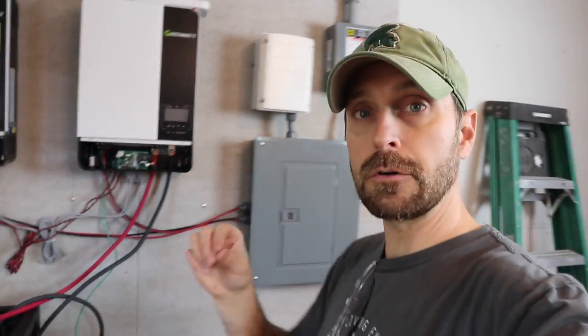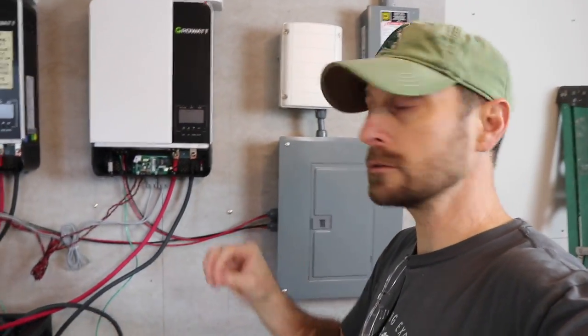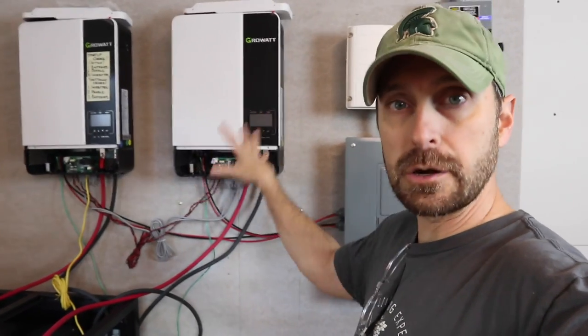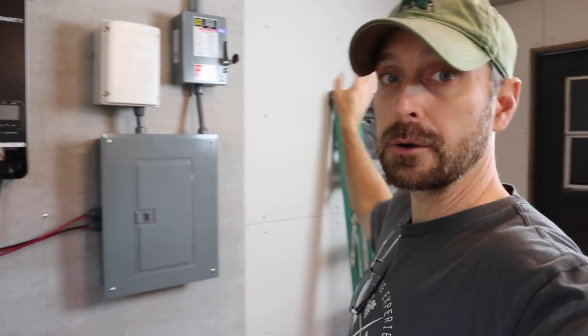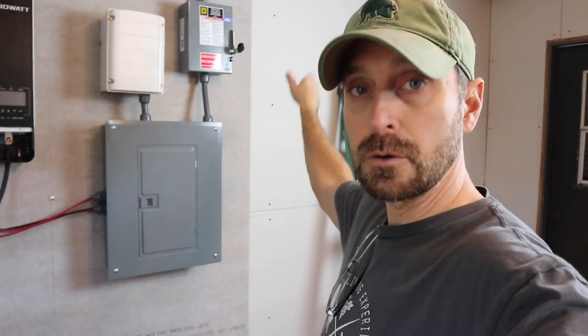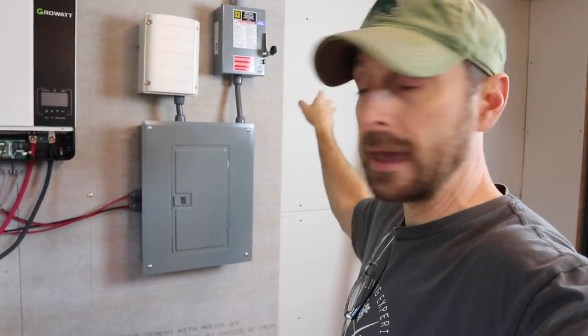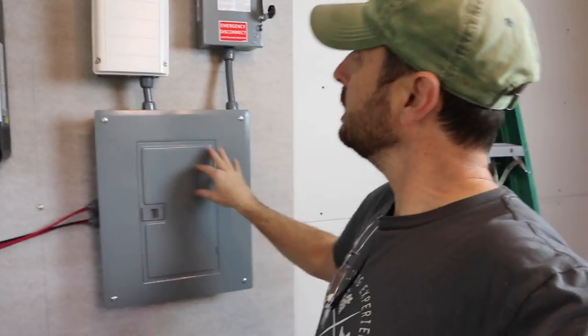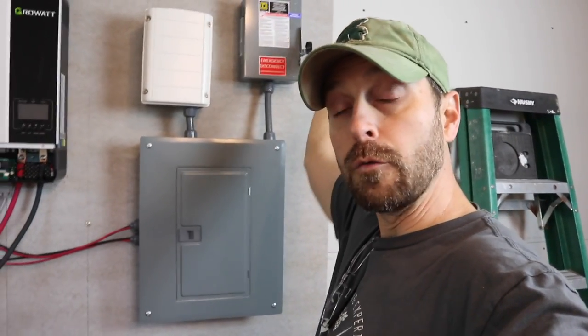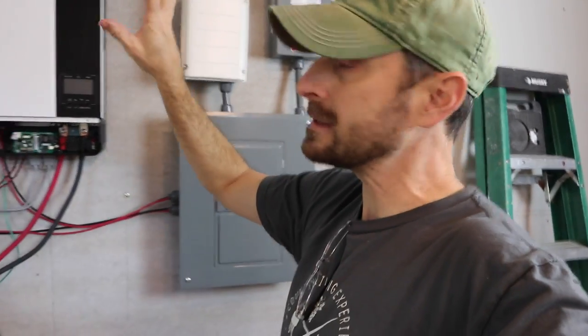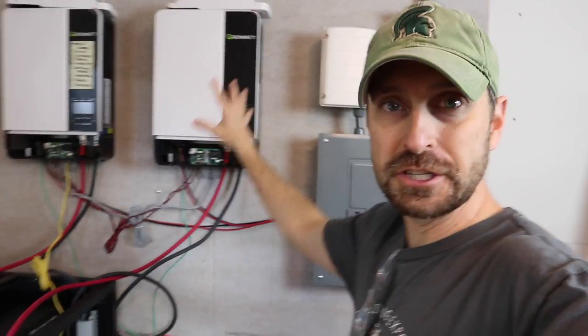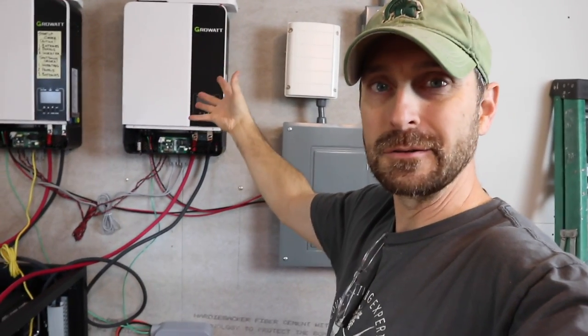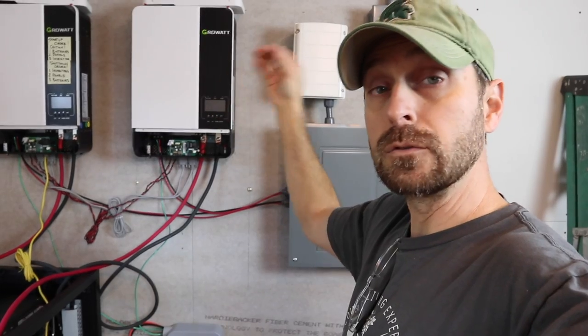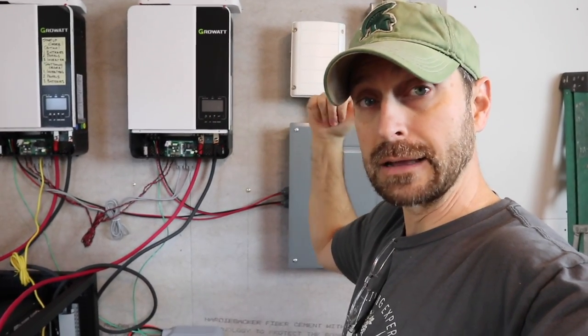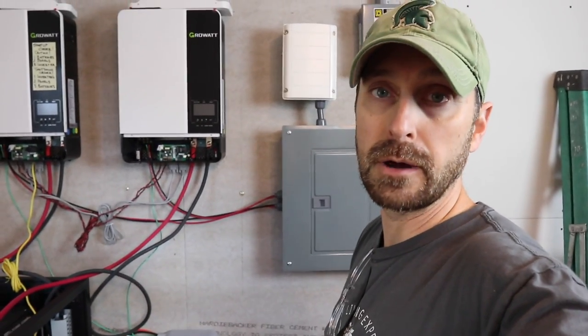And talking to several electricians, this is the right thing to do because this generates power and the grid generates power. That's connected to its own ground rod over there at the main panel. Everything here is grounded back over at the main panel, but this is a second power generation item, I guess you could say, or station, and you don't want that connected back there. So we've got that extra ground rod outside.